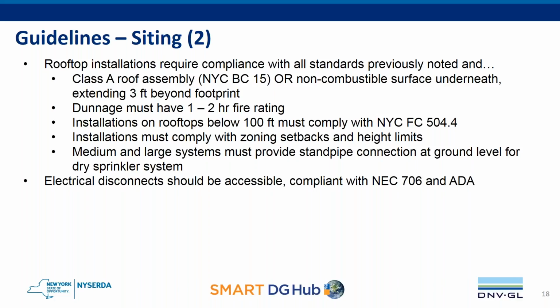For medium and large systems on rooftops, they must provide a standpipe connection at ground level for a dry sprinkler system or be interconnected with the building's sprinkler system automatically. In all cases, and as previously noted, there has to be an emergency stop on site, and that electrical disconnect should be accessible and compliant with NEC 706 and ADA.